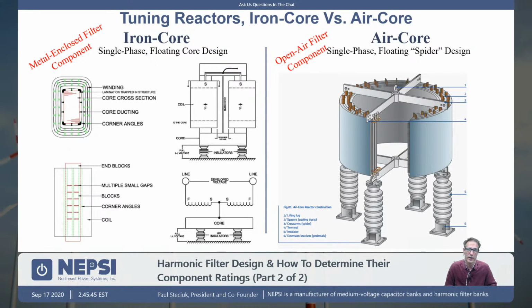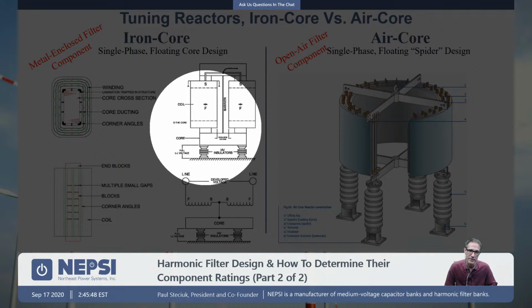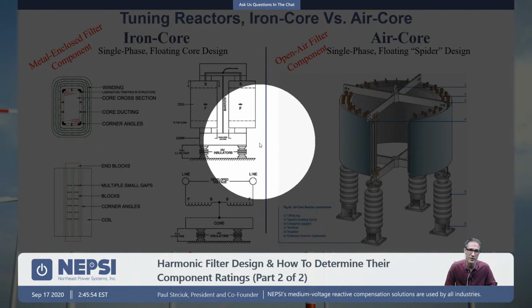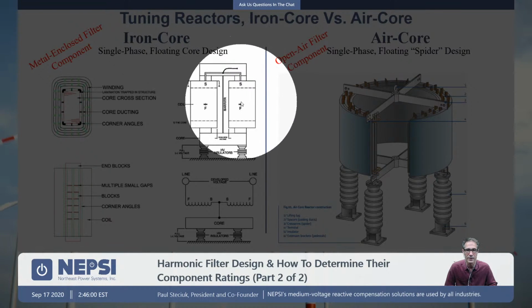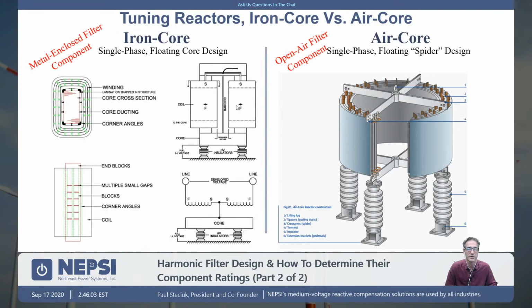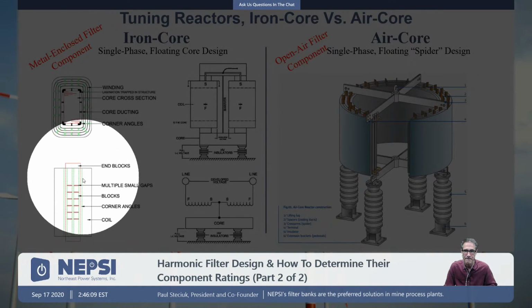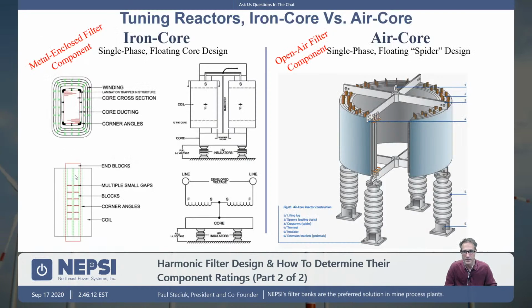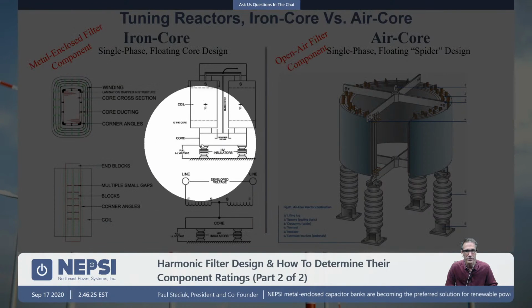So iron core reactor on the left, really the key difference here is that the iron is trapping the magnetic field. All right, there is no external magnetic field on an iron core reactor. The inductance is developed in air gaps that are embedded underneath the winding of this reactor. We use a distributed gap type design, kind of how we show it here. Okay, and that determines and makes for the inductance of the reactor. You can have single phase iron core reactors and three-phase iron core reactors. And I think I'll touch upon that in a moment. Here we're using a floating core design. It means that the reactor is put up on insulators.